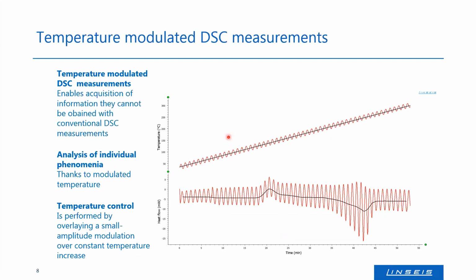The conventional DSC measurement is, for example, just a straight heating profile going upwards from room temperature to 300 degrees, for example for PET, what you can see here at the right. And this is the black curve. And below you can also find the DSC signal, the black curve here in the lower part of this diagram. And now what we do is we modulate the rising temperature with a pretty small modulation, but this is important, I will explain later. And this way we receive the red curve here at the bottom of this diagram. And due to this, we can receive much more information than in the conventional DSC heating run.